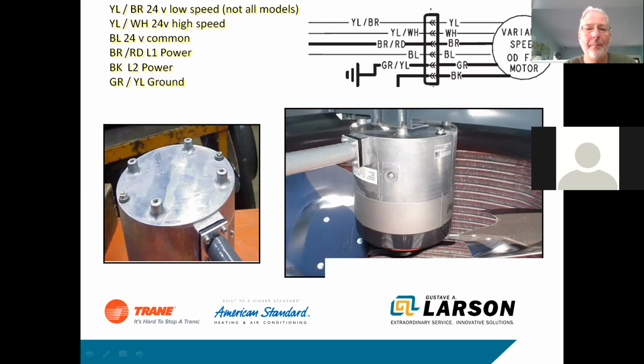So, the yellow-brown wire is a 24-volt signal to the motor for low speed on some models, and on the yellow-white wire, we get a 24-volt high speed. On the ECM motors, what you'll probably see is a blue and a yellow, or blue and a red wire going to the motor. That's a 24-volt low voltage signal. And there's also 230 volts going to the motor. The 230 volts is there at all times, and what turns that motor on is that 24-volt signal.